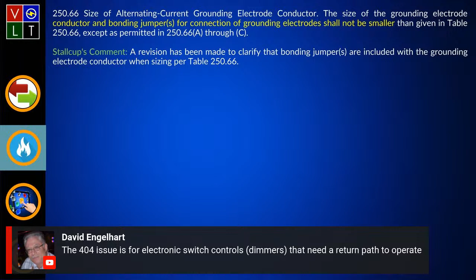Now, when you looked at the code making panel substantiation on this, and you were going to a concrete encased electrode, they even stated, and this wasn't passed by a narrow margin, this was a unanimous vote by the code making panel, that they even considered a number 6 grounding electrode conductor to be too small to connect to that concrete encased electrode. Now, the way the A through C reads, basically when they put that in, the opinion of the committee was...